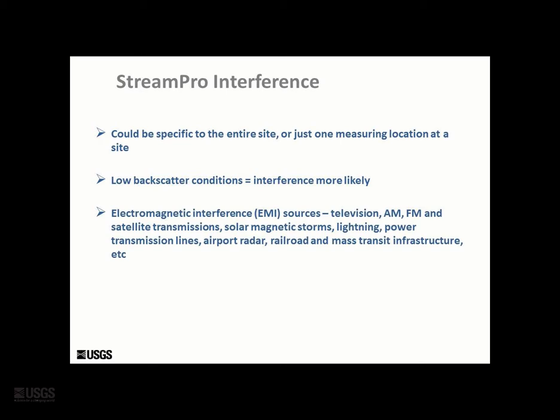Also, sites with a low backscatter condition are more susceptible to interference, as the EMI can more easily overwhelm the returns of the true signal transmitted by the ADCP. The cause of this interference is site-specific electromagnetic interference, or EMI.